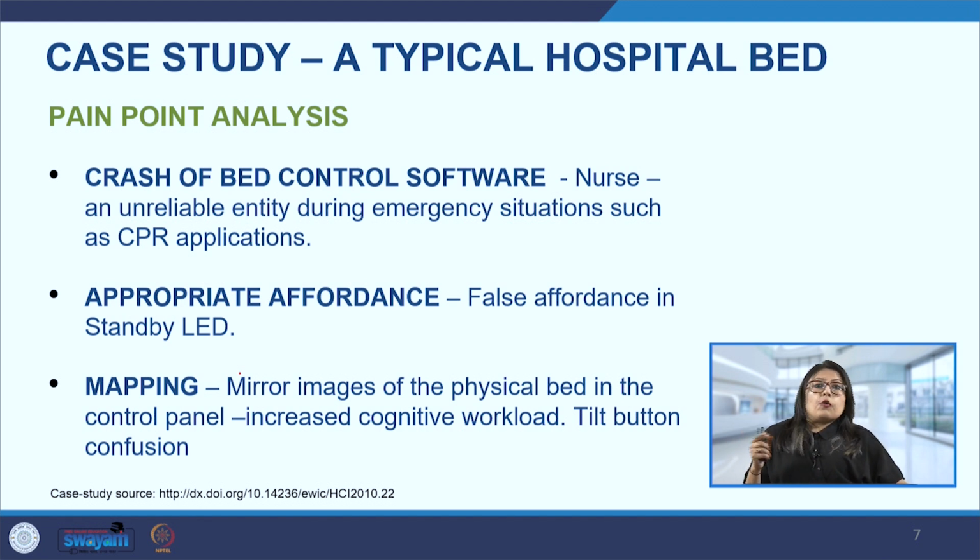So if we are tilting forward, will this control tilt the bed forward or backward? That was very confusing for the user, and they had to think before they pressed the button. Especially because it's a patient, who could be elderly, very frail, or badly hurt, we don't want to make them feel uncomfortable, and for this reason the mirror image was creating a lot of cognitive load on the user. And also the tilt button, the confusion about which side the bed will tilt, was a big point of confusion and led to a lot of pain for the users of these systems.